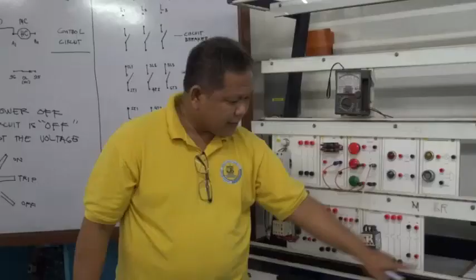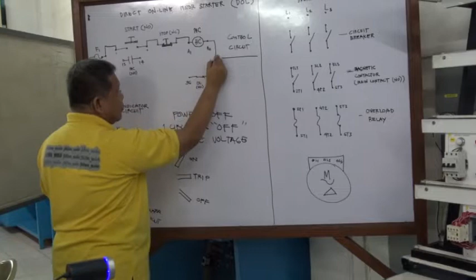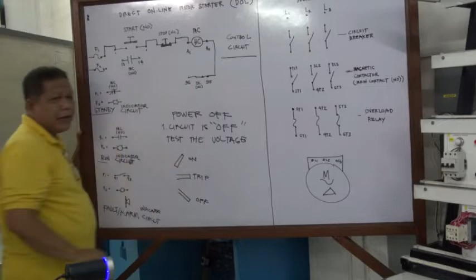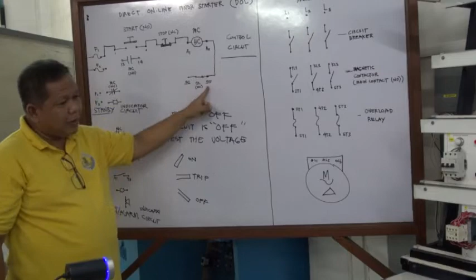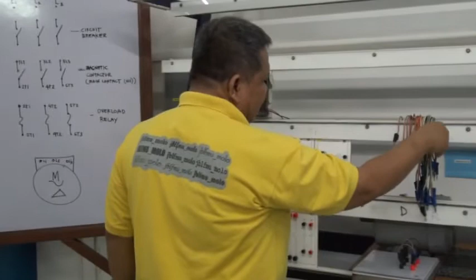Ayos? Now, A2 will be connected to terminal 95 of overload relay. Connected to terminal 95 of our overload relay. Okay, so again, we have to select wire.